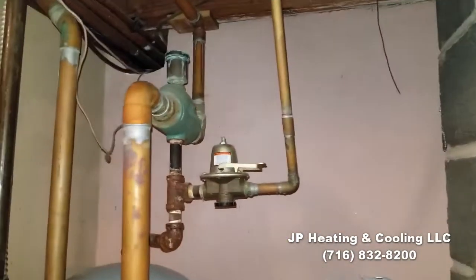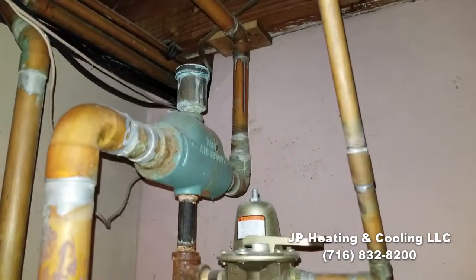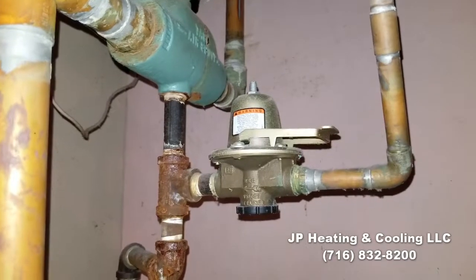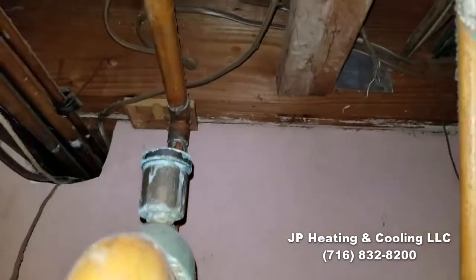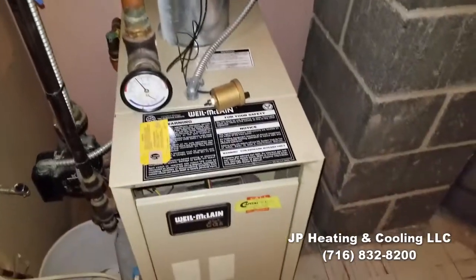Here we are back on another boiler repair. We're going to correct a whole lot of mistakes. This is a monoflow system that has a lot of air issues — a Weil-McLain boiler with monoflow piping, a single monoflow loop with a lot of branches.